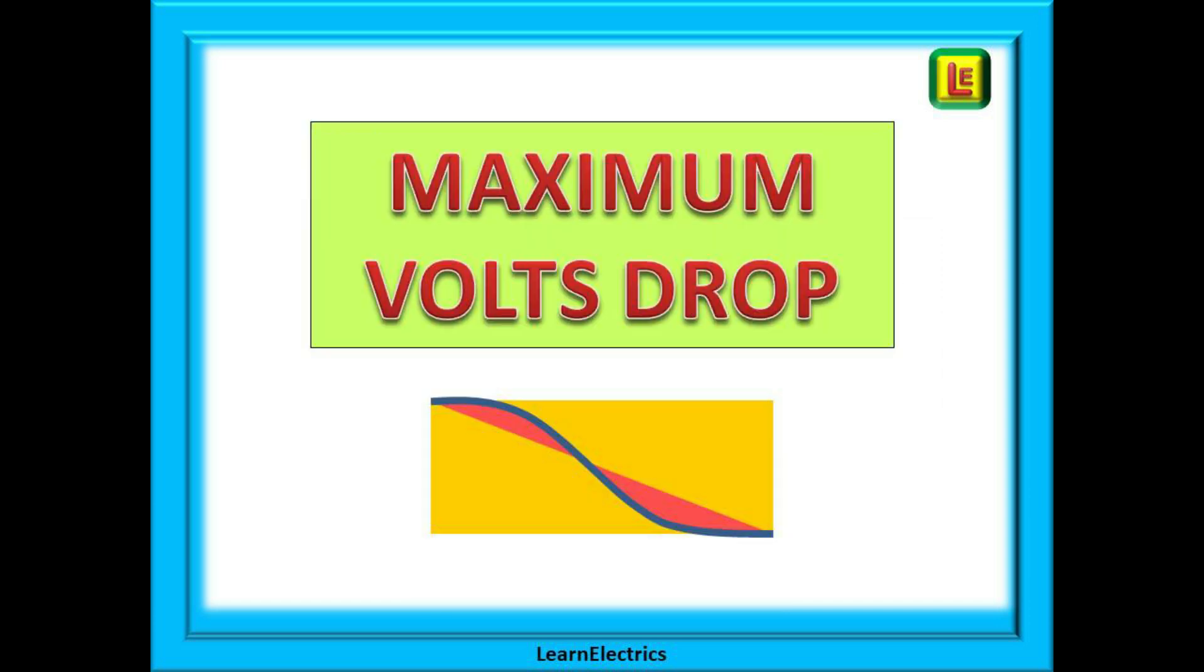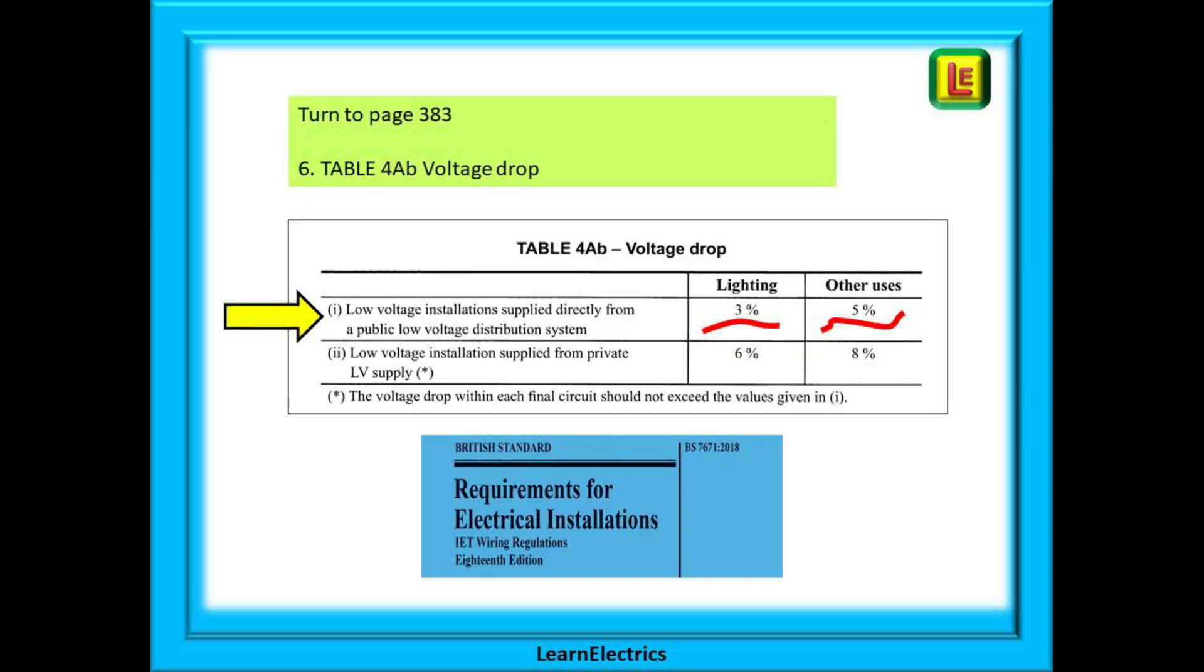Now we have this table, we can find the maximum permitted voltage drop. Table 4AB tells us that a low voltage installation supplied by a public distribution system, in other words the national grid, can have up to three percent voltage drop in a lighting circuit and up to five percent for any other circuit: the shower, the cooker, sockets, water heater, and so on.